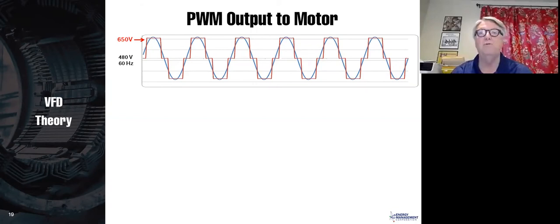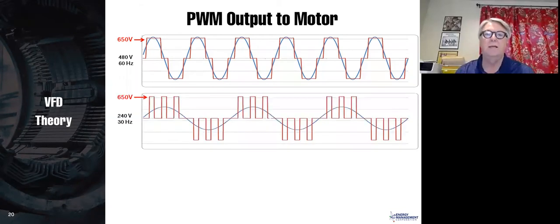Well, there have been a number of drive technologies for controlling the voltage. Some of them included changing the DC bus voltage level. But virtually all drives these days, low voltage drives, are PWM. And so PWM looks like this. Now, if I go to half speed, then I have to go to half voltage. The way I get that is to turn it on half the time and off half the time. So as you can see, we still have 650 volts. But if we turn it on half the time, off half the time, we will get effectively half of the voltage.